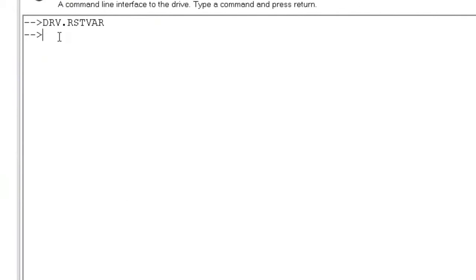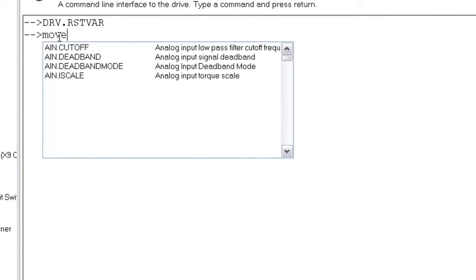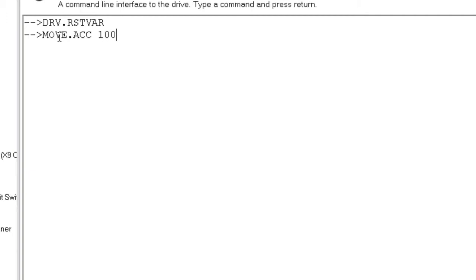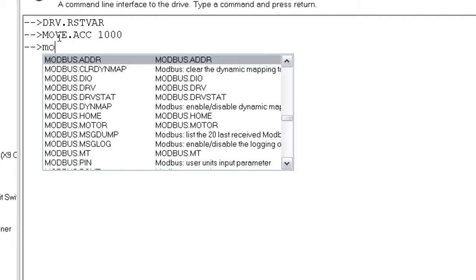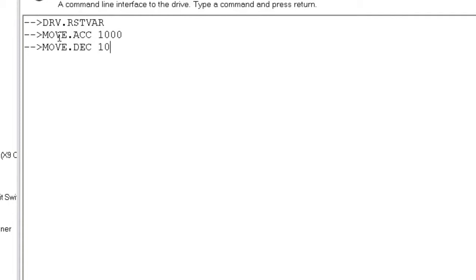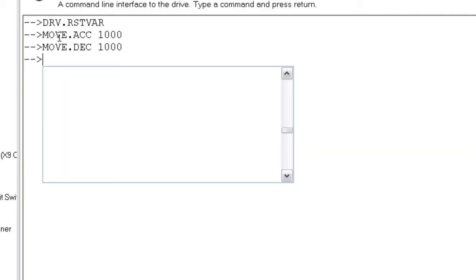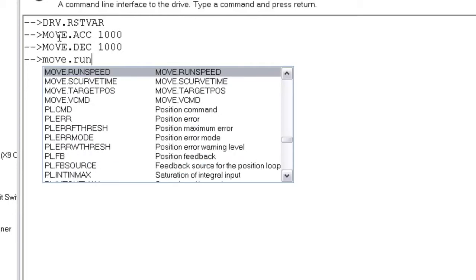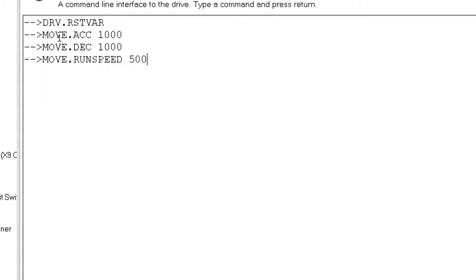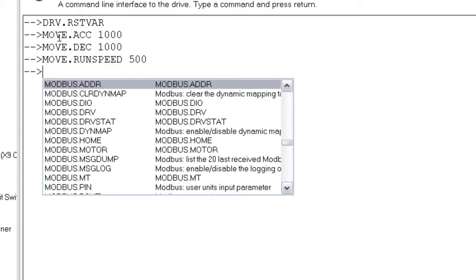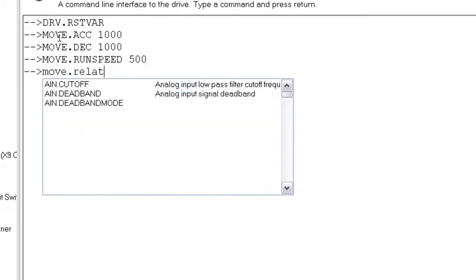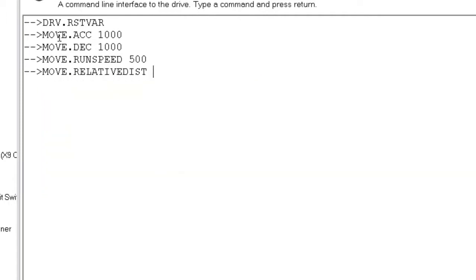Our move parameters will be entered as follows. Acceleration is move.acc and will equal 1,000, or 1,000 RPMs per second. Deceleration is move.dec and will also equal 1,000. Velocity is move.runspeed and equals 500, or 500 RPM. Distance is move.relativeDist and is 3,600, or 3,600 degrees, or 10 revolutions of the motor shaft.